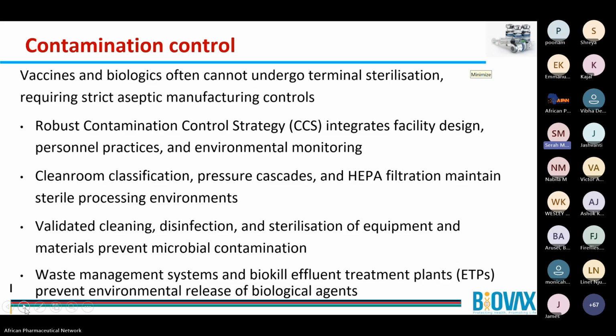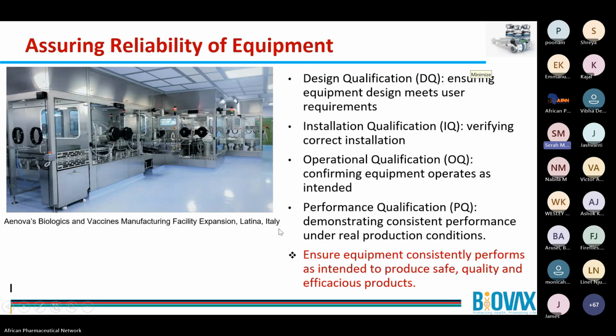And maybe something I've just remembered, when you're talking about the equipment, if you could go back, please, Juliet. This is when you're procuring the equipment. I focused on that because that is where we are at Kenya BioVax, but it's important to also note that during the life cycle of the equipment, you have to ensure that you have preventive maintenance of the equipment, and also you need to schedule calibration. So this is something that will help maintain your equipment.